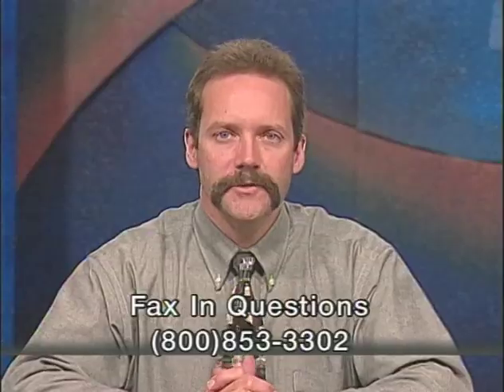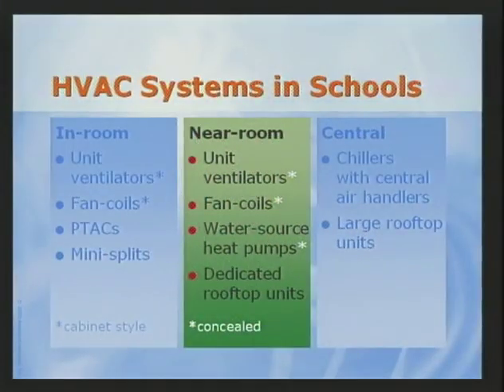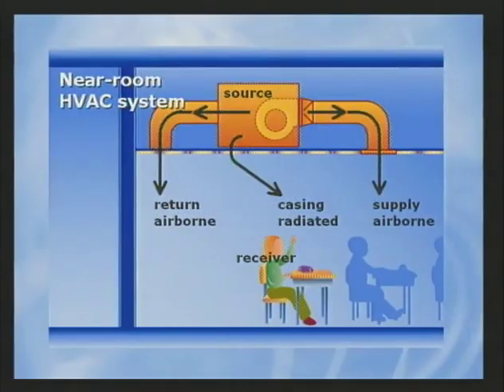Now, Dave, could you take us through what happens if we move the unit outside of the room? I think you called it a near-room unit? That's right. Near-room products offer a slight advantage to in-room products because the path is longer and offers opportunities for attenuation. Near-room products include concealed unit vents and fan coils, water source heat pumps, and rooftop units when they are dedicated to the room. For these units, sound typically travels along three paths from the source to the receiver: supply airborne, return airborne, and casing radiated.